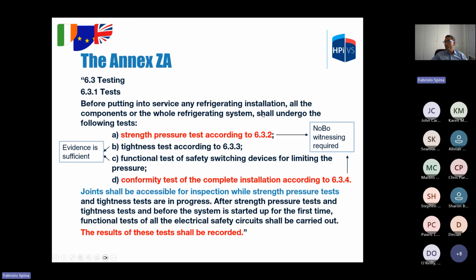The refrigeration installation must be subject to testing. These are the points described in the standard: the strength pressure test according to 6.3.2, which we will examine later, the tightness test, the functional test of the safety switching device, and a conformity test of the complete installation. For points A and D, the witnessing of the notified body is required. For points B and C, evidence is sufficient, so including evidence in the technical file is sufficient.